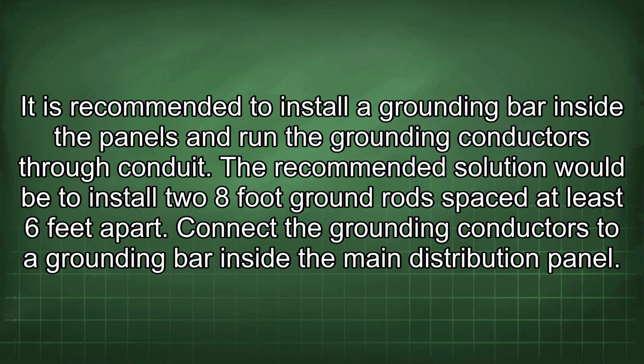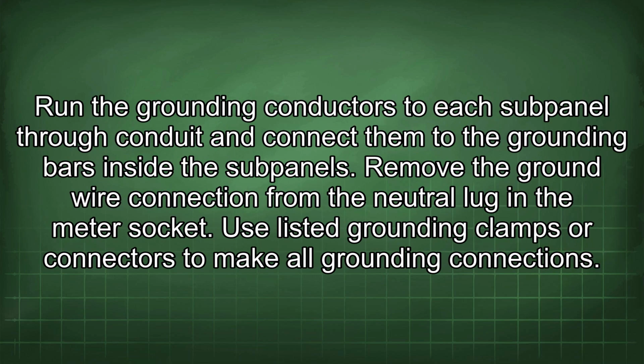The recommended solution would be to install 2 8-foot ground rods spaced at least 6 feet apart. Connect the grounding conductors to a grounding bar inside the main distribution panel. Run the grounding conductors to each subpanel through conduit and connect them to the grounding bars inside the subpanels. Remove the ground wire connection from the neutral lug in the meter socket. Use listed grounding clamps or connectors to make all grounding connections.